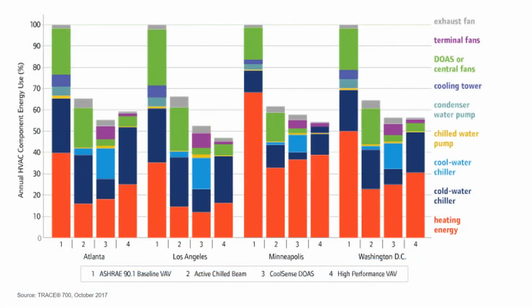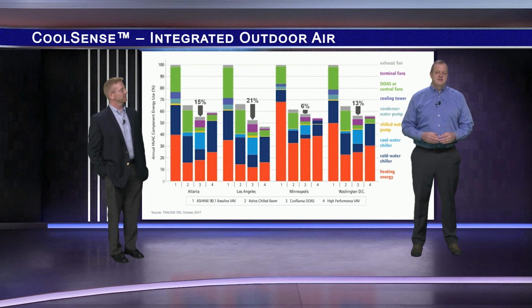Now for this example building, the CoolSense system, column 3, used less HVAC energy than the active chill beam system, which is column 2. About 15% less in Atlanta, 21% less in Los Angeles, 6% less in Minneapolis, and 13% less in Washington, D.C. There's more discussion of these results in the system catalog.